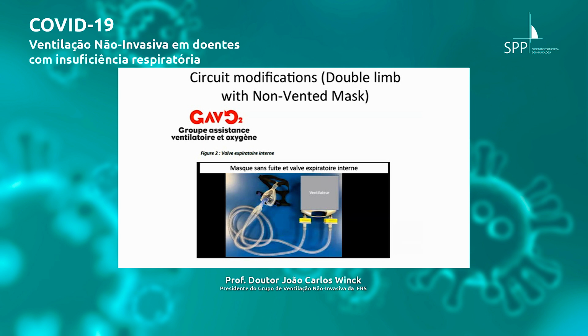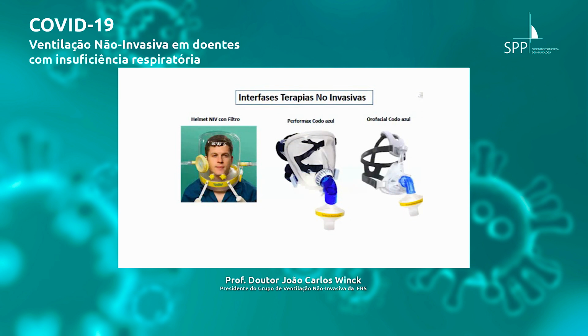Joao, it's not more safe, because anyway you are filtering the air in the same way. The problem with the system is one advantage and one disadvantage. The one advantage, you can monitor tidal volume. Also, you can get a very good estimation with the intentional leaks. If you use a Philips device, the Philips device is able to give you an estimation of tidal volume also with intentional leaks, as you know.